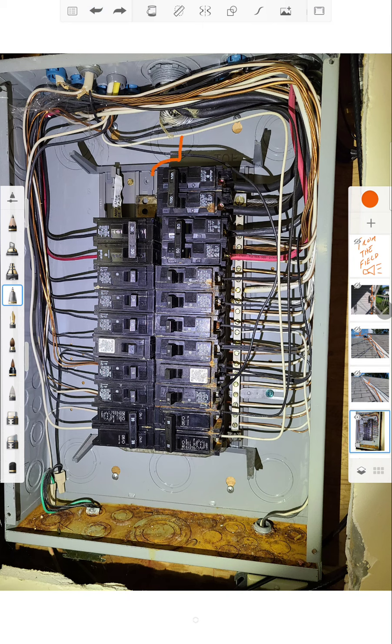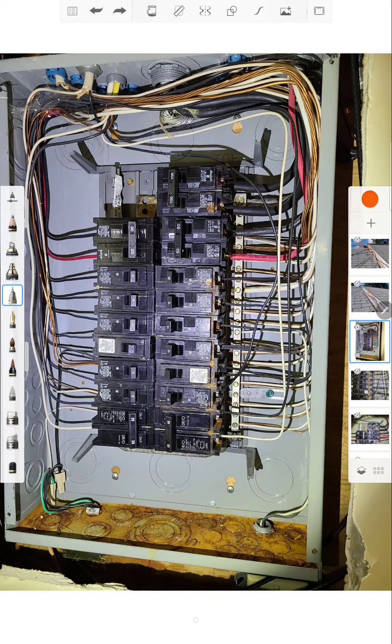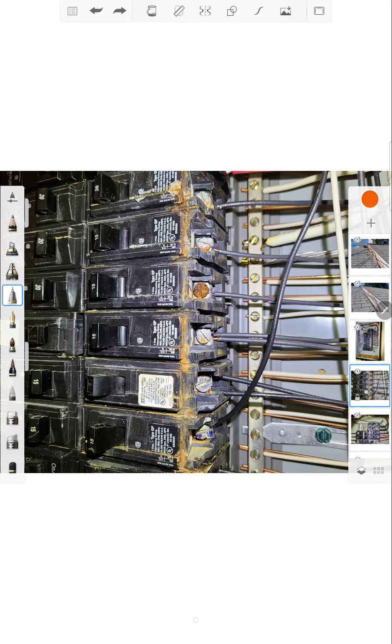So that water comes down here and works behind the circuit breakers, through the circuit breakers, all the way down to the bottom, which is why you're seeing it at the bottom. But as it's working its way down and through, you're getting corrosion at your connections, and you're getting corrosion behind the circuit breakers, most likely.